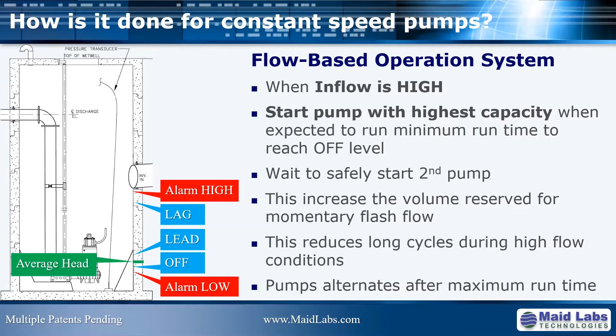You don't wait to get to the old lead level and run your pump for 2 hours or 3 hours. You start them as soon as you know that they will be running at least the minimum run time that is normal. What that does is that it will delay when you will start the lag pump by quite a lot, because now you have way more capacity to compensate for the actual flow coming in that could get above the lead level. And by delaying starting the lag pump, you will increase the overall efficiency of the entire lift station. So the next thing after that is, what do you do with variable speed pumps?